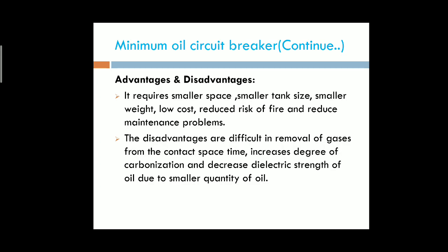Next, the main disadvantages of a minimum oil circuit breaker are the difficulty in removing the gases from the contact space in time, increased degree of carbonization, and decreased dielectric strength of the oil due to the smaller quantity of oil. These are the main advantages and disadvantages of minimum oil circuit breakers.